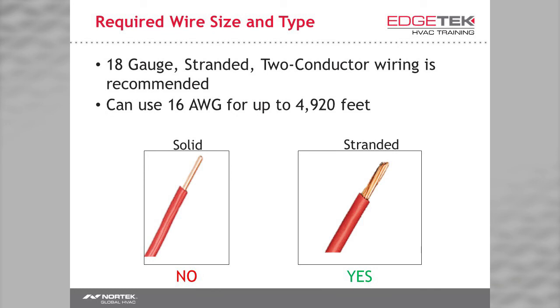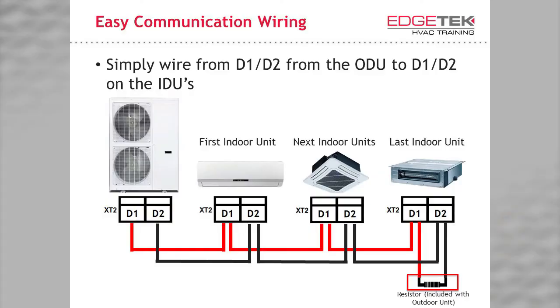Shielding is not required. If you use 16-gauge, you can run up to 4,920 feet, which should be more than enough. Please do not use solid wire like regular thermostat wire. Now, the question I would ask, will using a solid wire guarantee a communication error? No. Will we tell you to replace it if you do get communication errors? Absolutely.